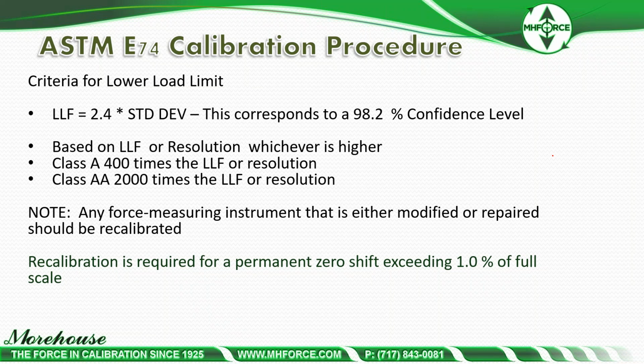If I have a resolution of 1 pound and I'm a Class AA device, 2,000 pounds is my first point. It could be where I have coarse resolution, where the lower limit factor multiplied by 2,000 or 400 is actually less than the resolution. And therefore we would have to use the first test point as the resolution times 2,000 versus the lower limit factor times 2,000, whichever is higher.